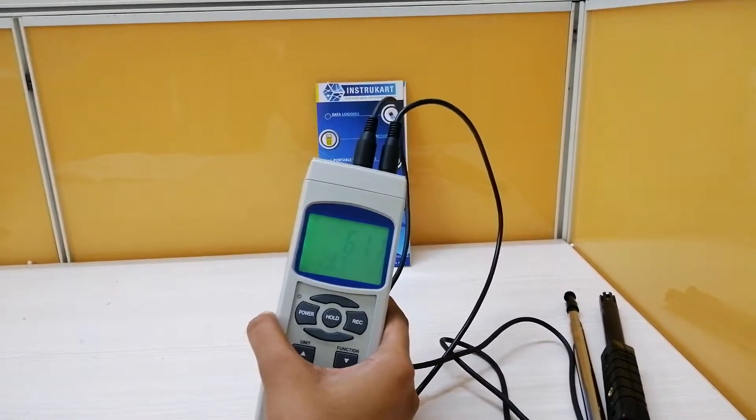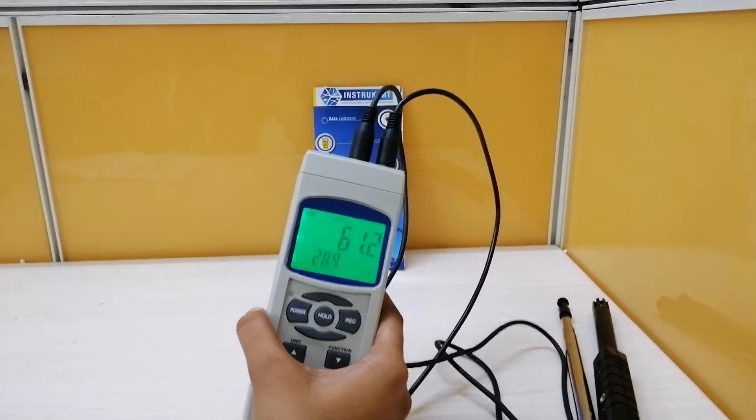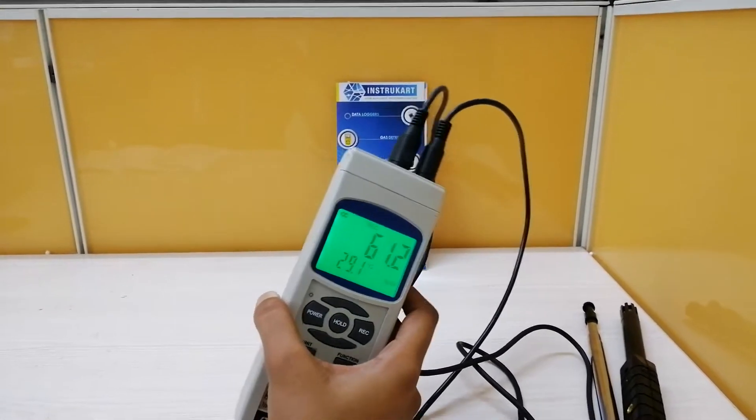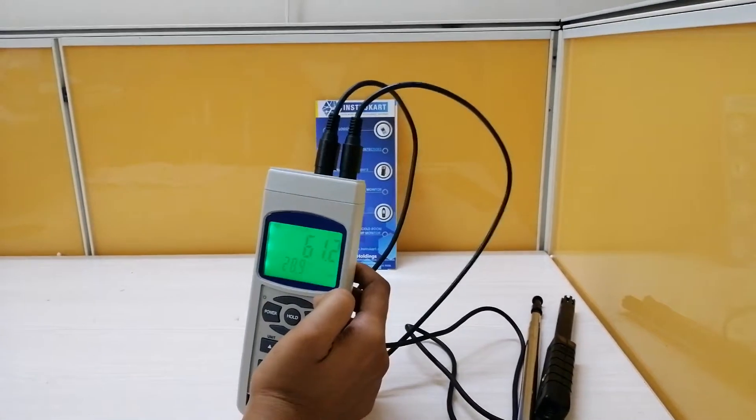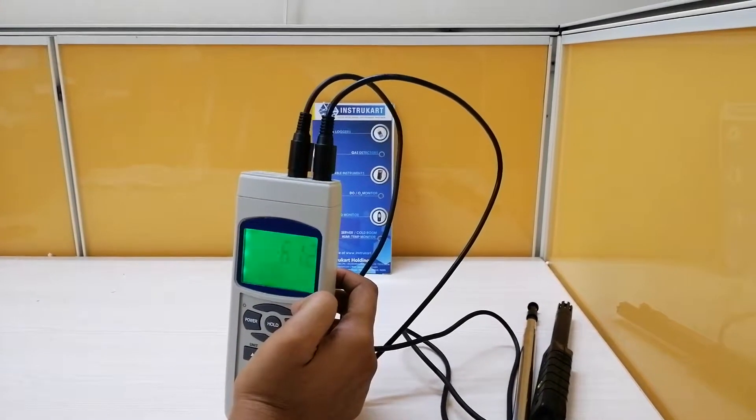There is a special parameter for this anemometer. It comes with a provision for RS232 USB for PC computer interface, and it has data hold, maximum and minimum recording. You can also see the real-time data as I have told with the SD card.